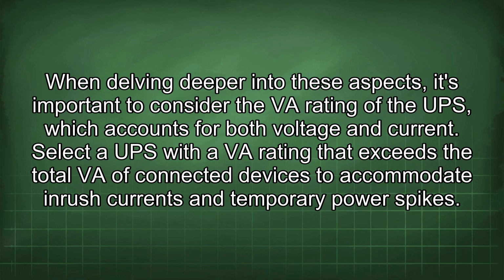When delving deeper into these aspects, it's important to consider the VA rating of the UPS, which accounts for both voltage and current. Select a UPS with a VA rating that exceeds the total VA of connected devices to accommodate inrush currents and temporary power spikes.